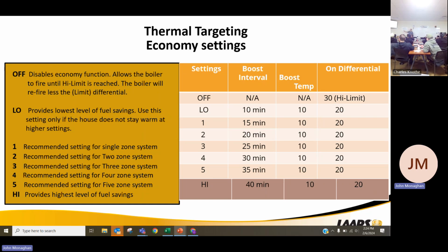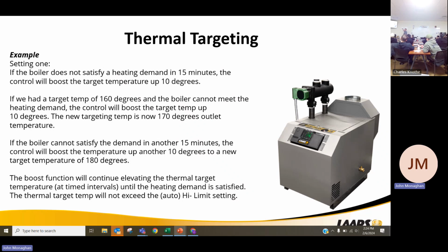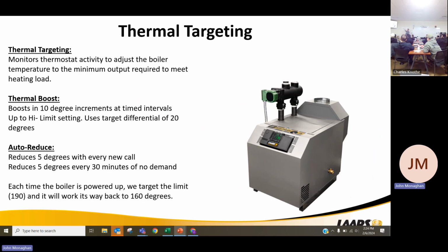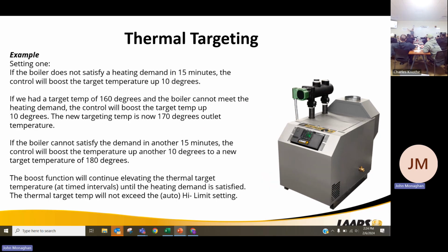So thermal targeting, this is basically how it's going to come set up. We'll use an example. We have a target temp of 160 degrees. The boiler does not meet that demand. It's going to raise the temperature up to 170 until the demand's satisfied. So what it's going to do, if that demand target was 160 and the boiler shut off at 150, the new set point temperature is going to be 155. It's looking to drive the boiler to its lowest water supply temperature possible.